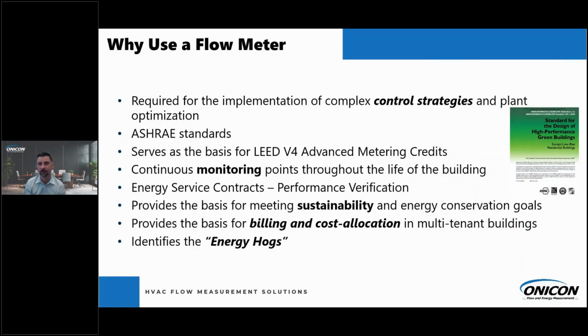So why are we using flow meters? I have a lot of reasons listed here, but I like to break this down to three main applications: monitoring, controlling, and billing. It's great to have multiple points of monitoring so you can see what's happening through your system. Also, we use these flow meters all the time for controlling, whether controlling your chiller plant or your data center, having information to tell you, hey, when do I want to turn on that second chiller? When do I want to turn on that third chiller? And then the third one, billing applications.